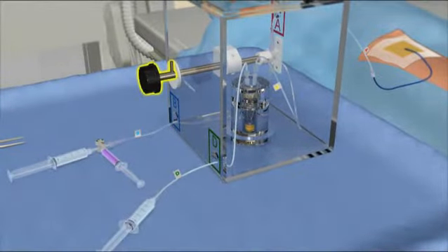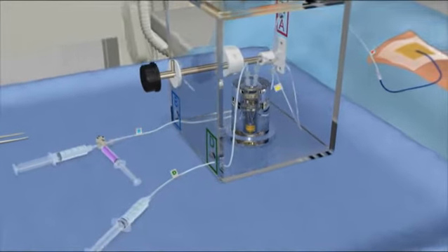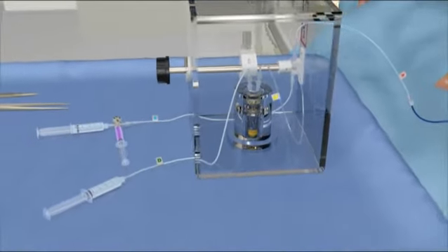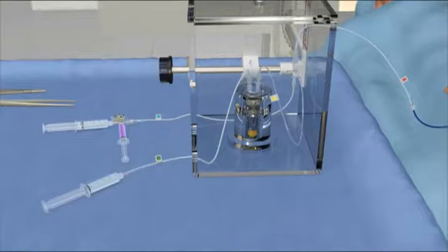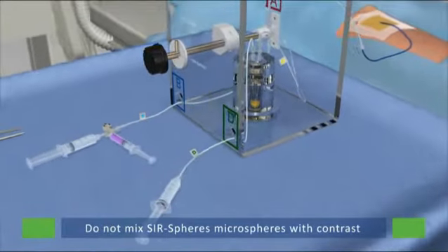Check the control knob is in the 12 o'clock position, and inject 2 to 3 milliliters of sterile water for injection from the B line to check that the microcatheter and A line are securely connected. A hand contrast run can be performed prior to the microsphere administration to double-check the catheter position. Be sure to flush the B line with enough water for injection to wash out the contrast. Mixing of contrast and Sirtex microspheres will cause clumping of the spheres and catheter occlusion.